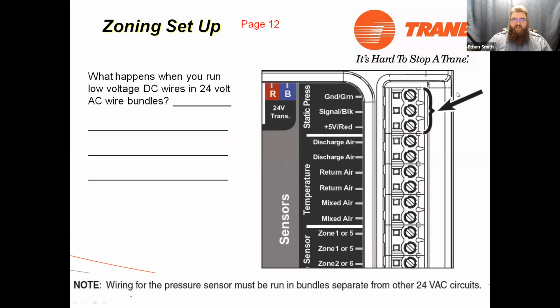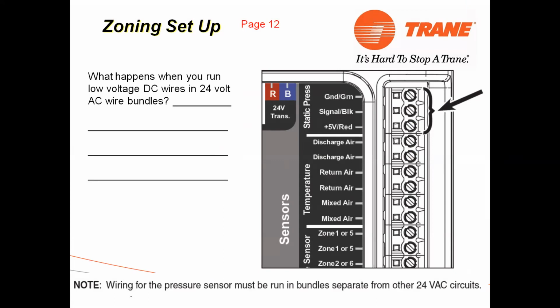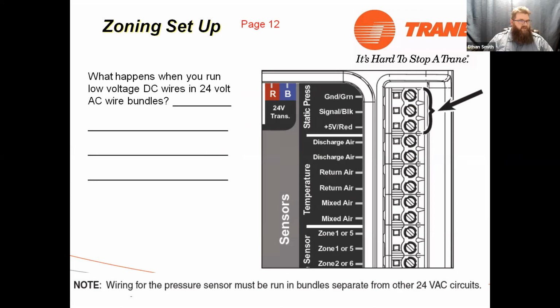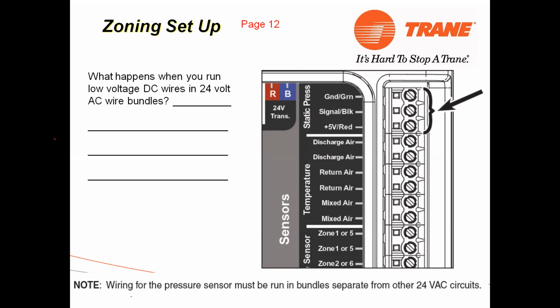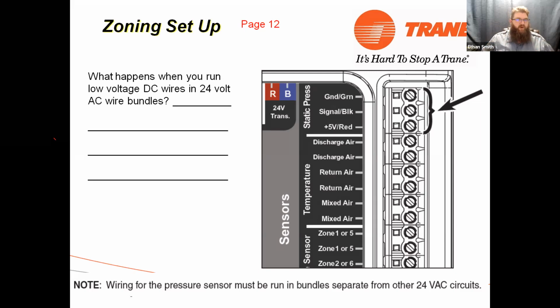The static pressure sensor is a 5-volt DC device. So anybody who's had experience with 5-volt devices knows that you do not run those wires in bundles with other wires. Anyone tell me why? Picks up interference. Okay, it's going to pick up interference from the current running through the other wires. Absolutely. Okay, so when you're running that static pressure sensor, make sure that you run it separately.